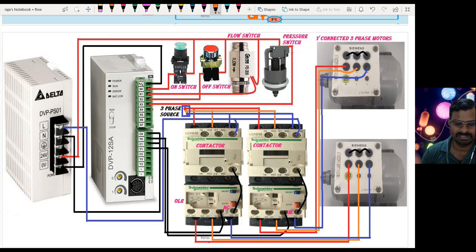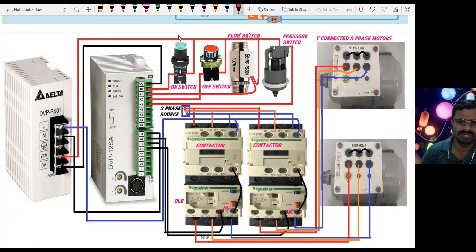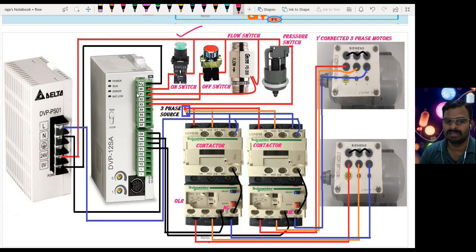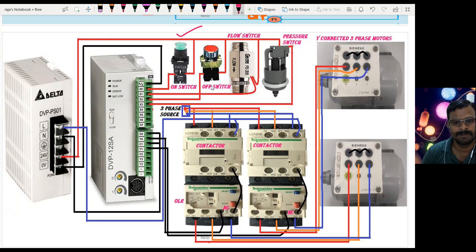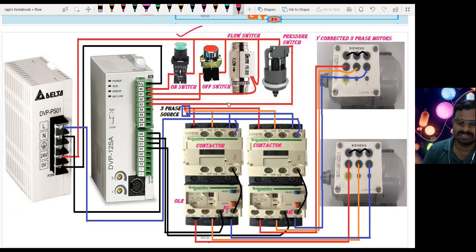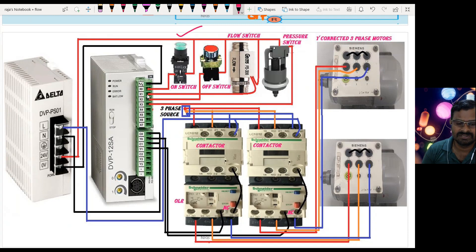When we operate the on switch, the supply is transferred to the PLC input side, and according to the program the control relay gets on. It then waits for the pressure switch to give a signal. Once the pressure switch gives a signal, that input is received at X3, and the lube oil pump turns on. When the pump is on, fluid flows to the flow switch. When the flow switch detects flow, it gives a signal at X1, which switches on the compressor motor.